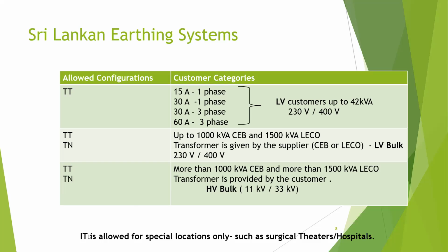And now we are coming to the IT system. The IT system is the one I told you about earlier. In an IT system, the source side is isolated. Because of that isolation, there is no circuit connection, so the circuit will not complete even if there is a fault through your exposed conductive path.